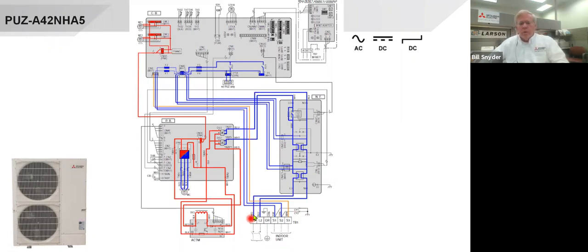So we come through with L1 and L2, we come through the noise filter board. We come out of the noise filter board up to this main PC board. You'll notice there's two fuses here, F1 and F2. And then we come back to S1 and S2. So essentially, L1 and L2 power coming in should be what you read on S1 and S2. In some of these diagrams, you'll see it literally goes immediately from L1 to S1, L2 to S2.